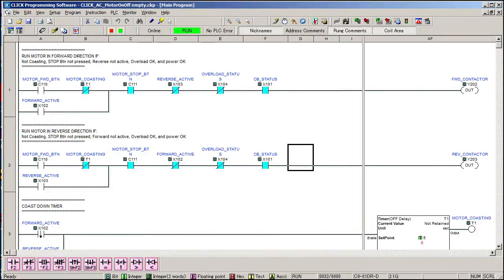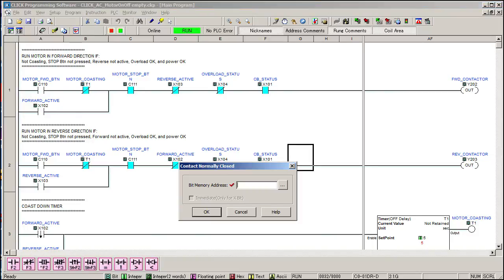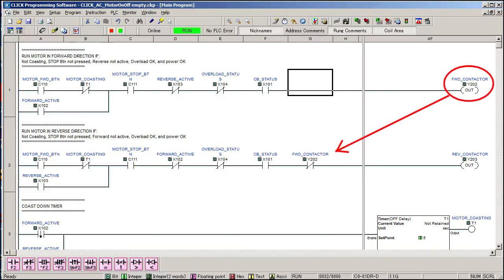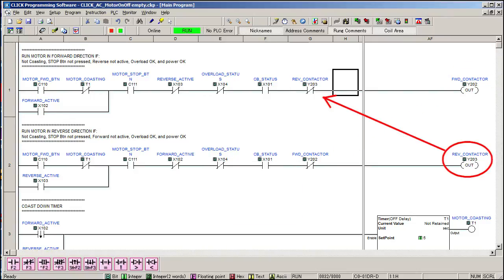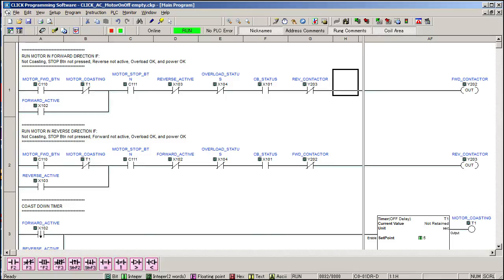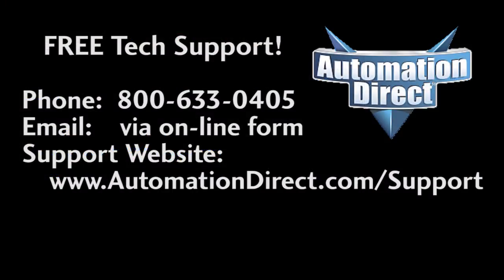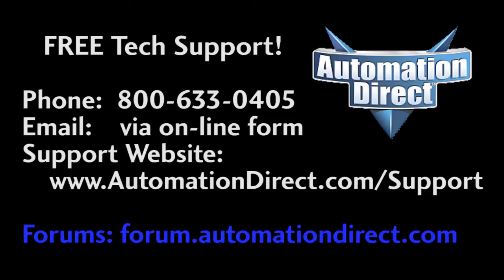One side note, you could add another contact here that says don't reverse the motor if the forward contactor is active and the opposite here. But since the mechanical interlock already has it covered, we didn't add that in this example. But if you don't have access to a mechanical interlock, this is the next best thing. And as always, if you have any questions or need any help, please don't hesitate to contact AutomationDirect's free award winning tech support. They will be happy to help you. And don't forget the forums, there are lots of folks there that love to share their years of experience. Just don't post any support questions there, tech support doesn't monitor the forums on a regular basis.